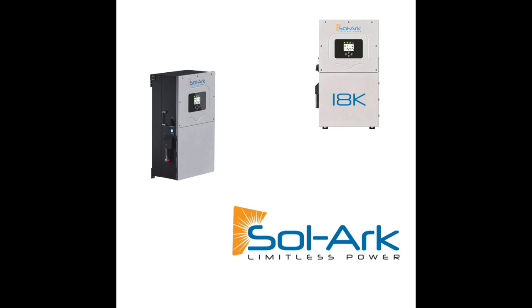And really what I like about this battery specifically, it can actually charge at much lower temperatures than other lithium iron phosphate batteries without heating. I'm not sure what the exact temperature range is, but I know it can go a little bit below freezing and still charge appropriately, while most other lithium iron phosphate batteries will require maybe a DIN rail heating mount inside the module, or maybe heating pads between the modules itself. So this is a little more cost efficient in terms of batteries in colder climates. So as long as it's within the appropriate operating range for those colder climates and the charging range, I think it'd be a great solution for those up north.